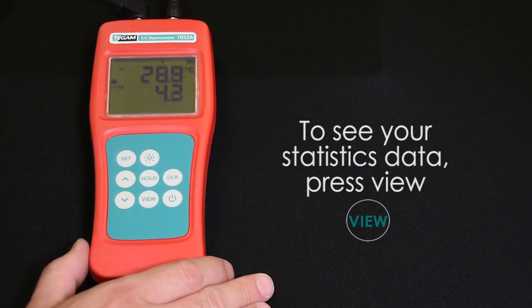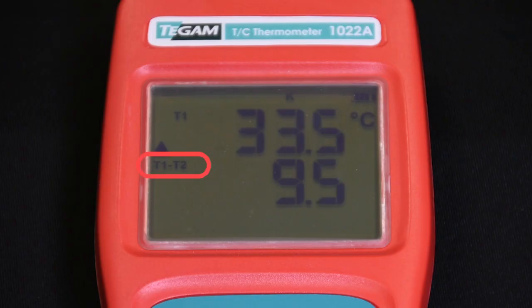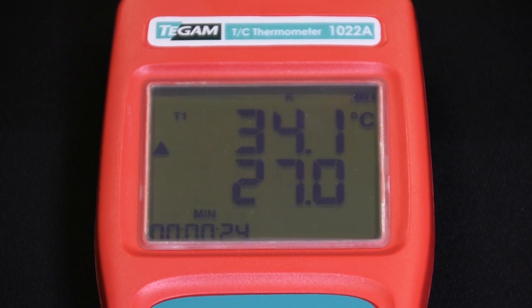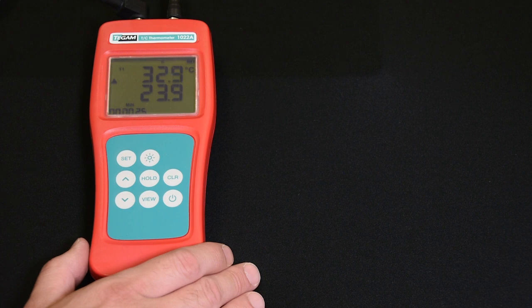For single channel models, the first statistic will be displayed on the LCD. For dual channel models, the T1 minus T2 value will be displayed. Just press View one more time and the first statistic will be displayed. The Channel 1 minimum statistic is displayed. This is the minimum value since the instrument was turned on and the last time Clear was pressed.